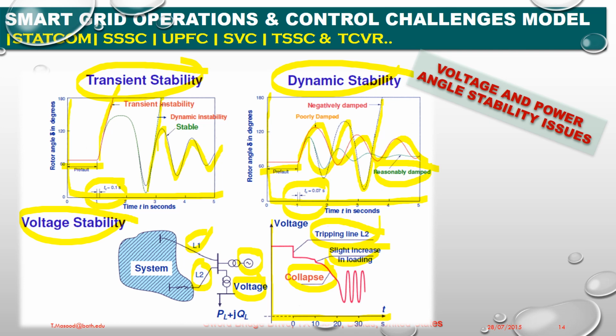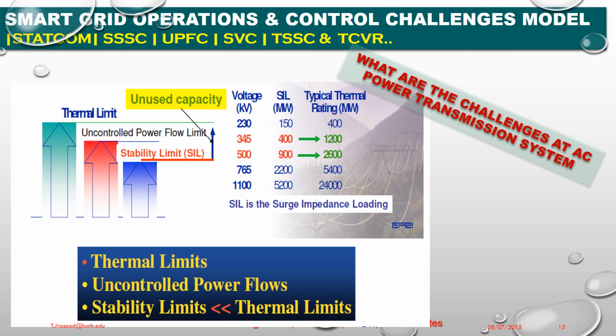On my next slide, we are going to discuss the thermal limit of the AC power transmission system and why we need FACTS devices to implement these solutions. What are the challenges of the AC power transmission system? As per the EPRI analysis or database, this is my voltage, this is my SIL, and this is a typical thermal rating. For 230 kV, SIL is 150 and thermal rating 400. Similarly, 345, 400, 1200, and 500, 900, 2600. If my line is operating at 500 kV line voltage, my SIL will be 900 and thermal rating can go up to 2600.